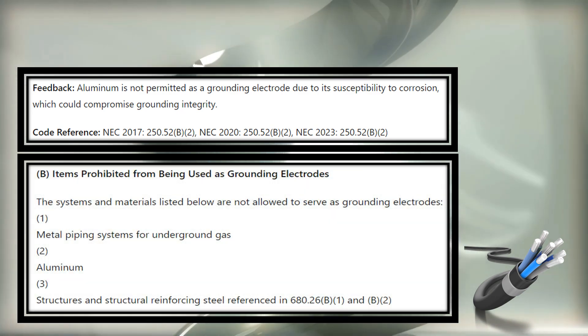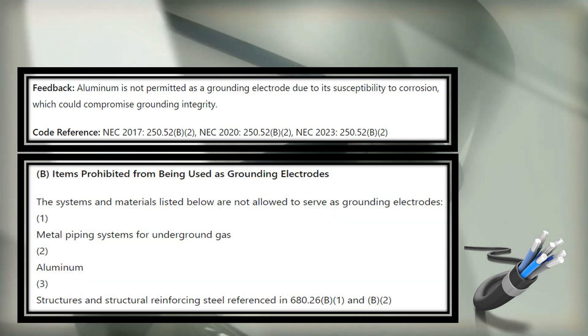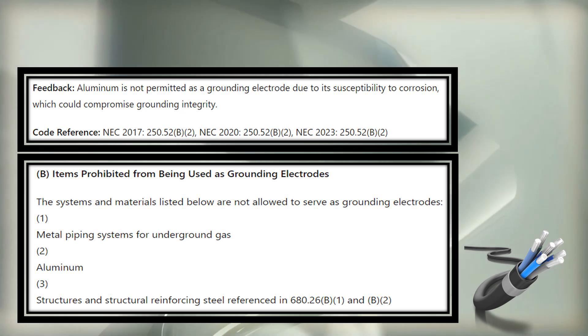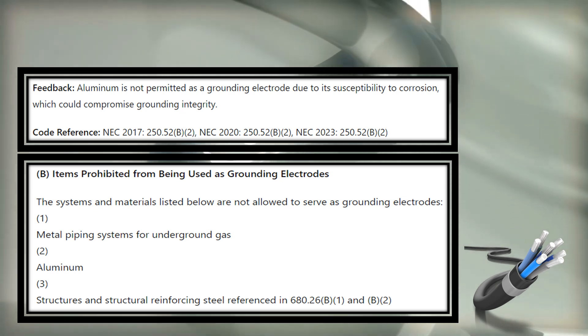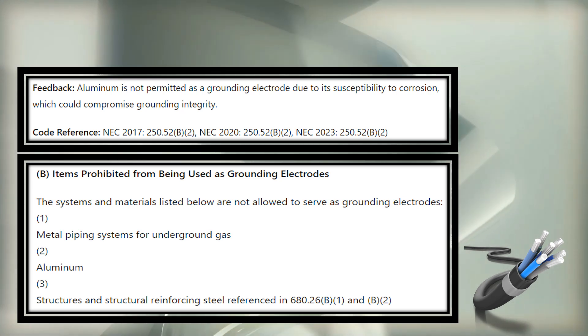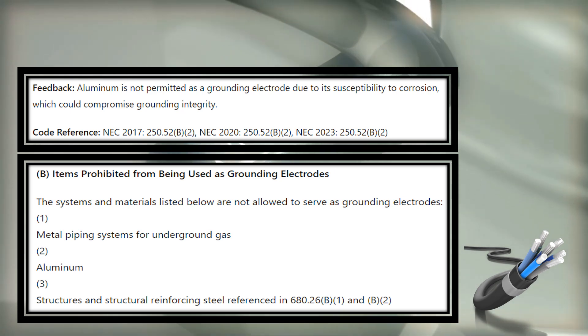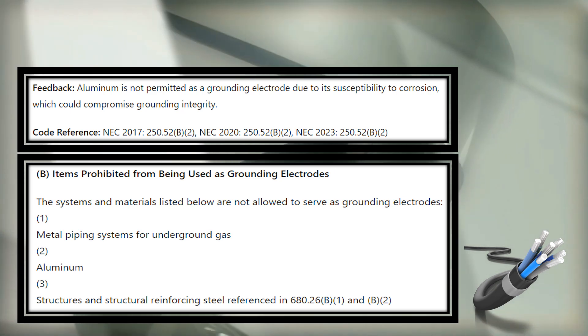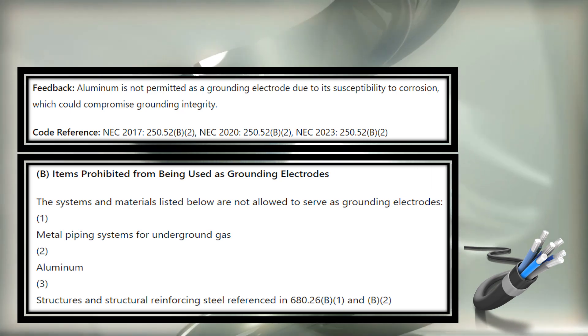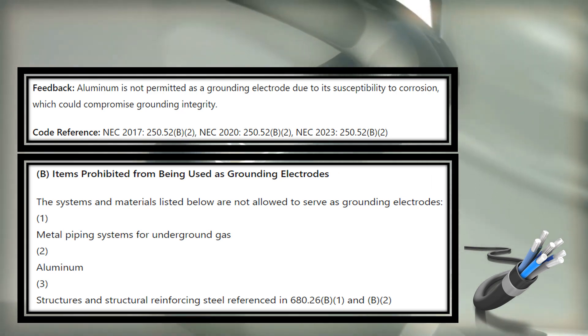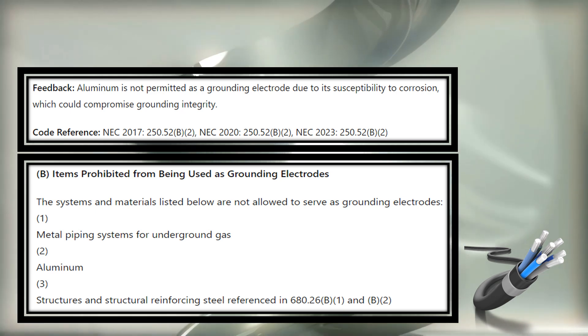When we head over there, there are a few things that we are not allowed to use as a grounding electrode. B1 is metal piping systems for underground gas — we don't want to use those as part of the grounding electrode system. Aluminum is specifically called out as well.